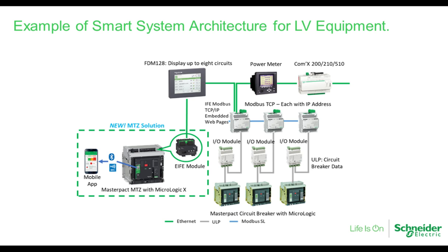So again, now we can take all that digital information, bring it up to a software and monitor it and look at it from all kinds of different aspects, from thermal, from overload to power quality and what's happening. And again, with those Bluetooth devices, we can also look at it, like I said, right on our smartphone, or get alerts to what's happening to that system. So we can get alarms and alerts so we know ahead of time or when something is happening right away. So those are some of the examples that we can use while digitizing our equipment. Today's equipment or older equipment does not have these capabilities and cannot provide you that information. And again, a lot of our failures, unfortunately, Murphy's Law indicates they're going to happen at the wrong time in the wrong place and right in the middle of a long production process.